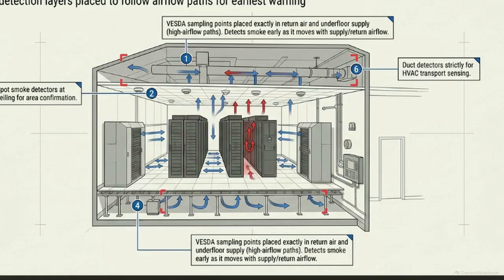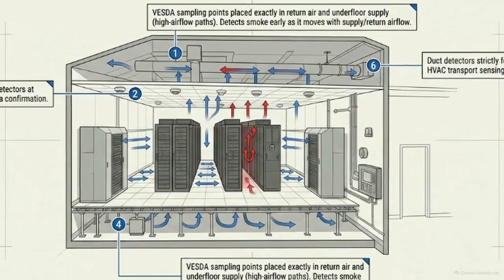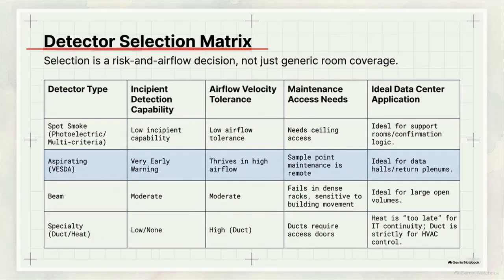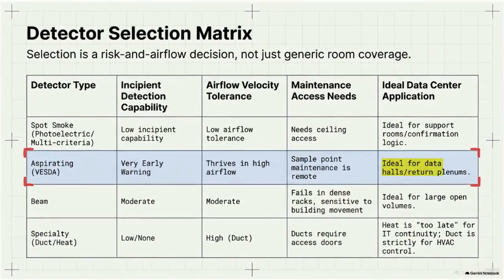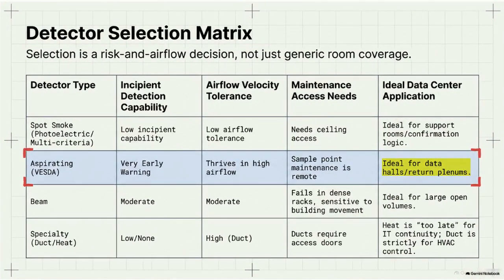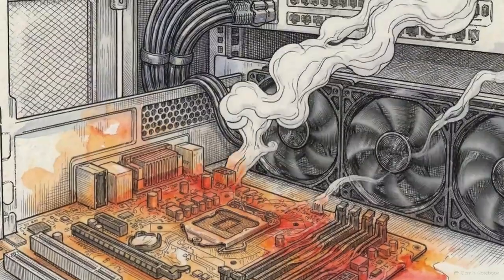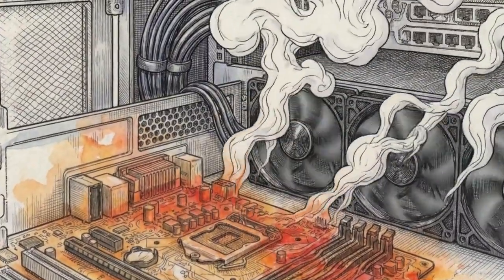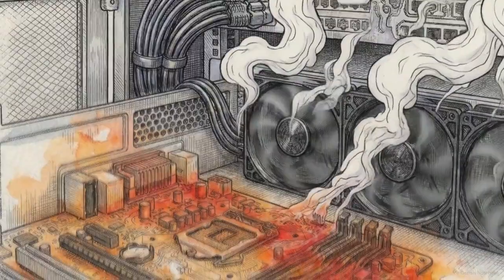This diagram shows smoke forced into return air plenums and underfloor supply. To catch that smoke, aspirating sampling points at positions 1 and 4 are positioned exactly within these high-velocity paths. This detector selection matrix compares technical applications across the facility. High airflow data halls require aspirating, or VESDA technology, because it thrives in these high-velocity environments where other sensors remain blind. If the system isn't hunting smoke along HVAC return paths, operators won't know there is a problem until thermal damage is already irreversible.